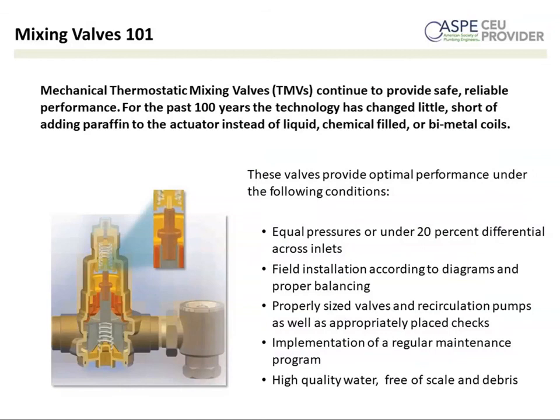So mechanical mixing valves, this is focusing a little bit more on the master mixing type valves, the large thermostatic distribution valves. So these, again, we've talked about earlier in the presentation. You've got liquid-filled, chemical-filled, bimetal, paraffin. There's lots of different approaches to this. But they provide very good performance, but obviously optimal conditions are critical. So having relatively equal pressure is very important. Making sure that the installation is correct. Right, making sure that these are installed properly. From time to time, every once in a while, we'll see the hot and the cold pipe backwards, but that's kind of a rare case.